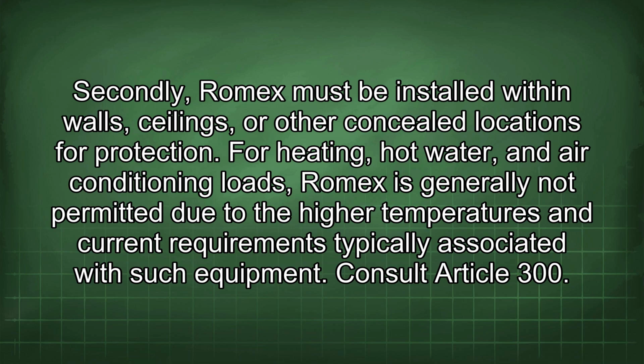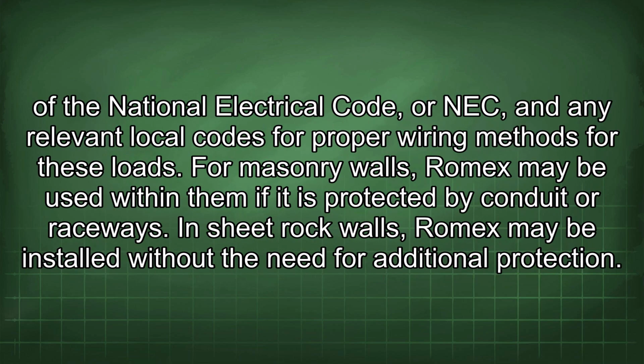For heating, hot water, and air conditioning loads, Romex is generally not permitted due to the higher temperatures and current requirements typically associated with such equipment. Consult Article 300 of the National Electrical Code, or NEC, and any relevant local codes for proper wiring methods for these loads. For masonry walls, Romex may be used within them if it is protected by conduit or raceways. In sheetrock walls, Romex may be installed without the need for additional protection.